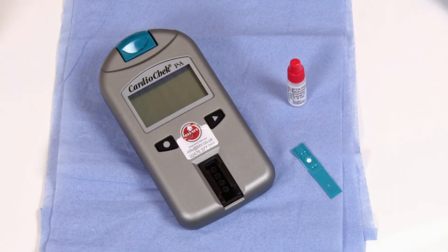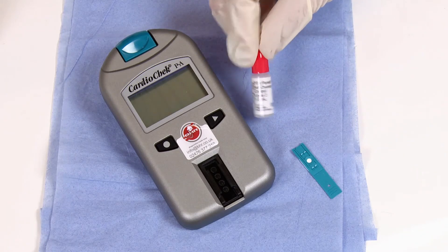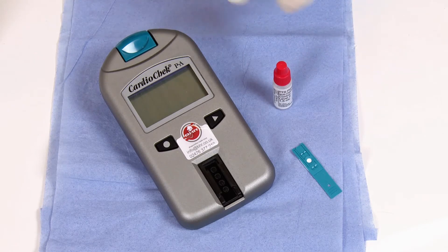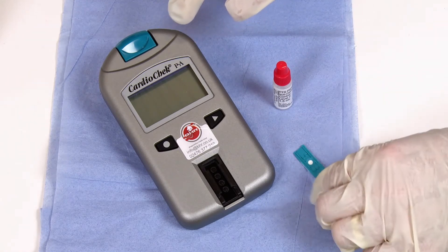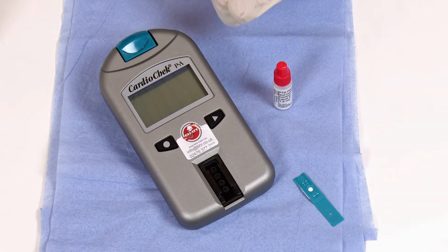This is a guide to run an IQC test on the CardioChek analyzer. This control solution verifies the performance of your entire analytical system — both the meter and the test strip are tested to ensure they are working properly. To turn the analyzer on, press either button on the front.